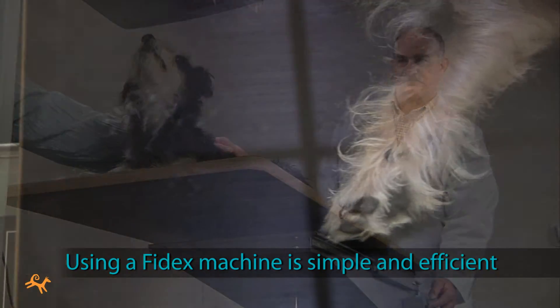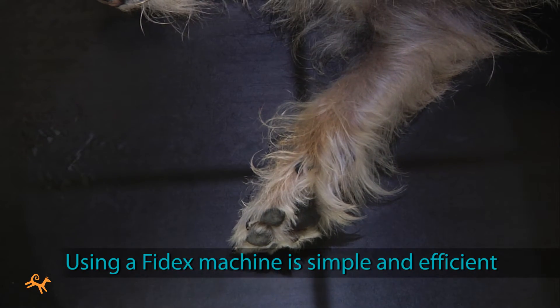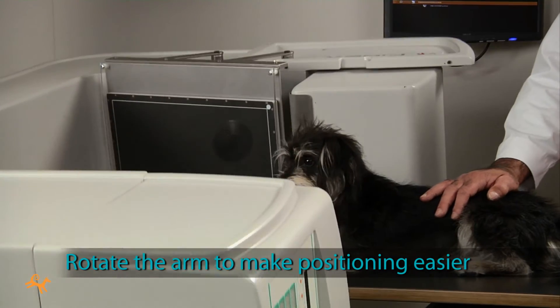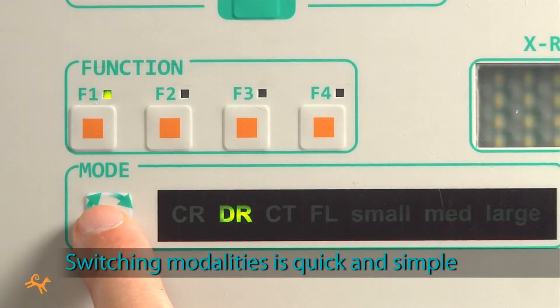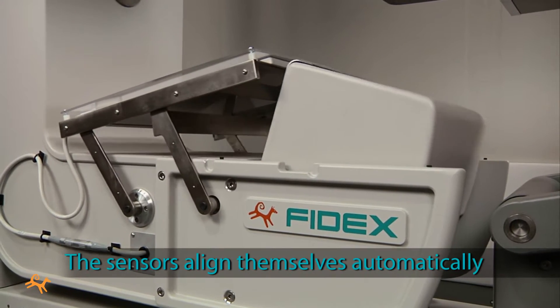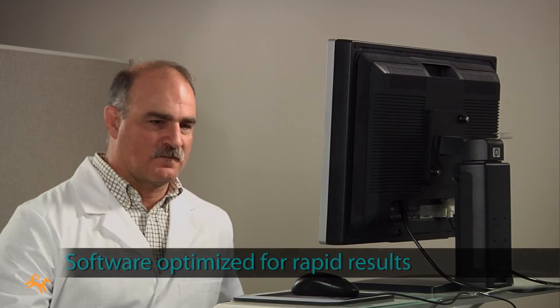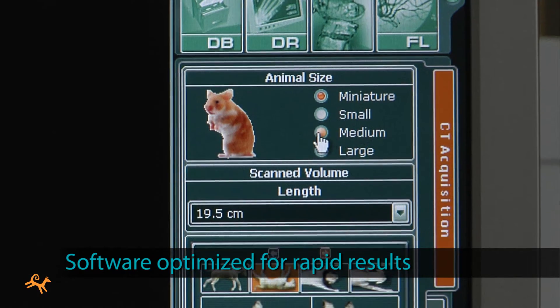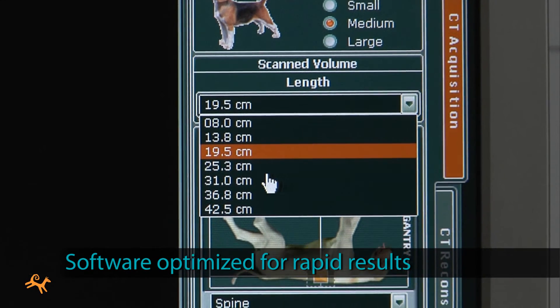Using a Fidex machine is simple and efficient. The patient positioning system works smoothly and quickly. For 2D x-rays and fluoroscopy, you can rotate the arm to make positioning far easier. Switching between modalities is also quick and simple — the sensors change over and align themselves automatically. At the console, setup and operation is streamlined, with software optimized specifically for rapid results in veterinary settings with minimal training.